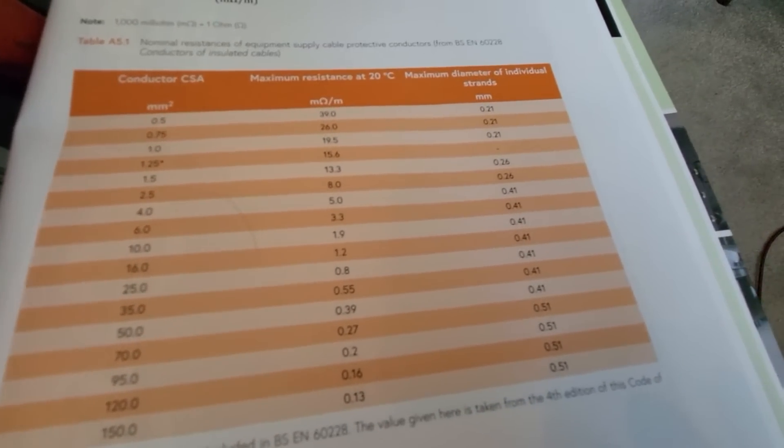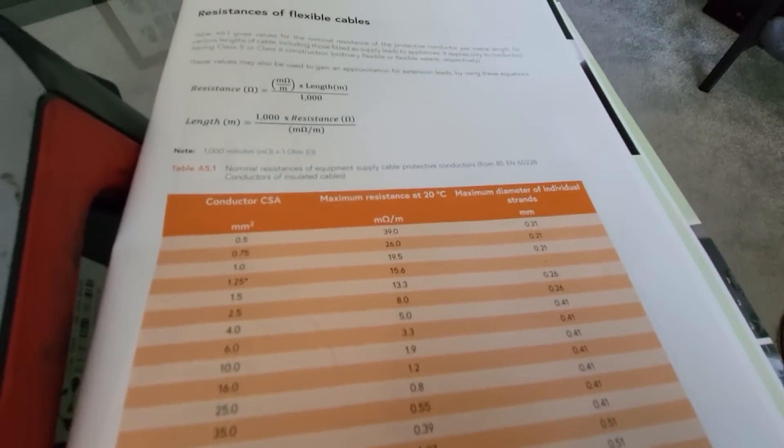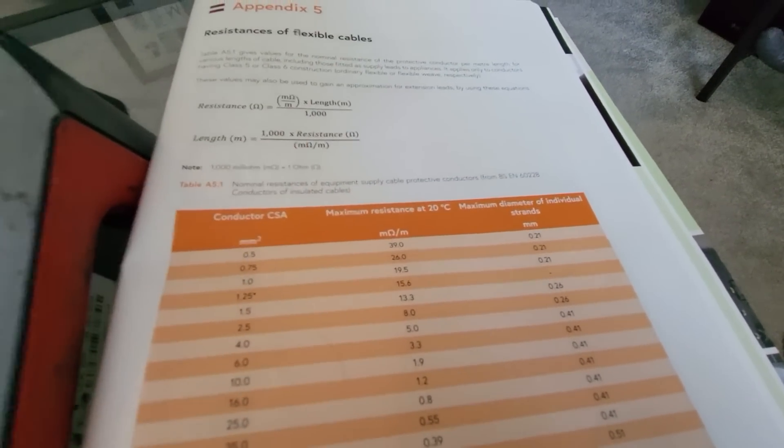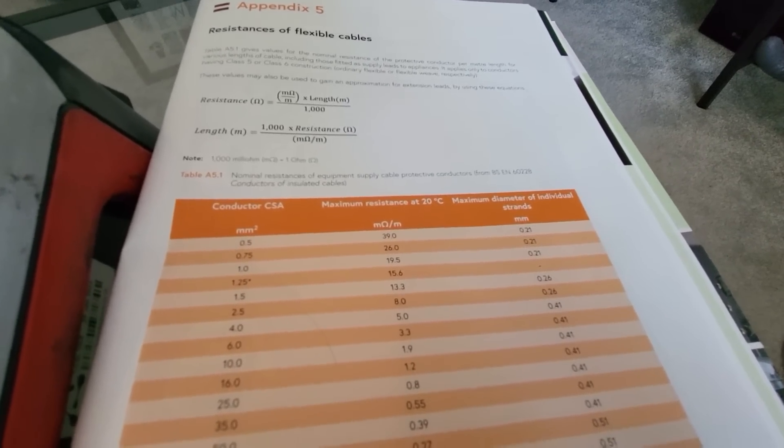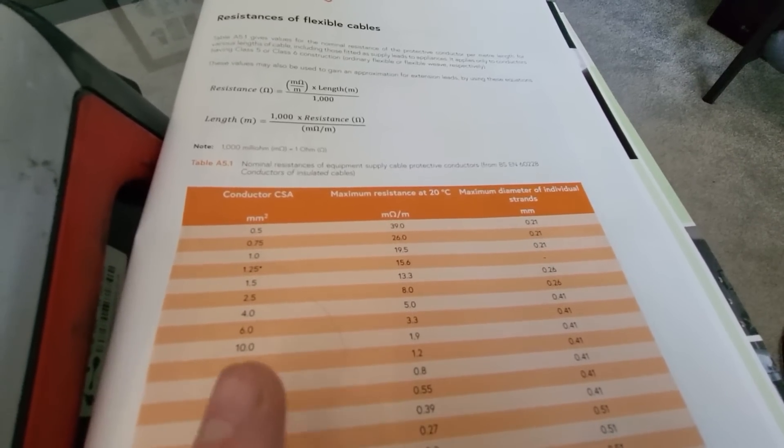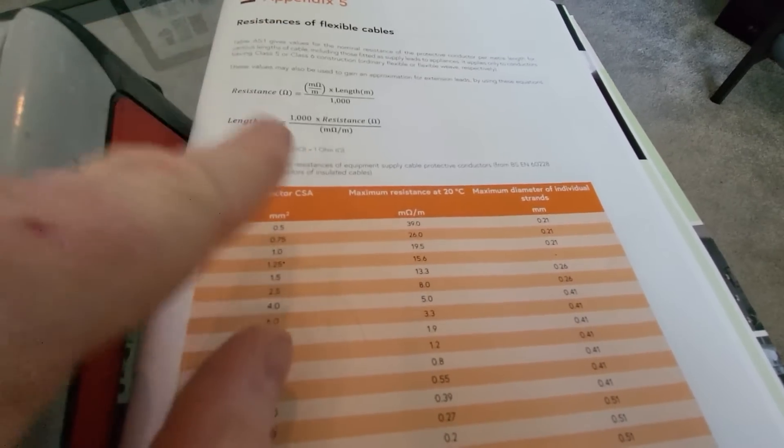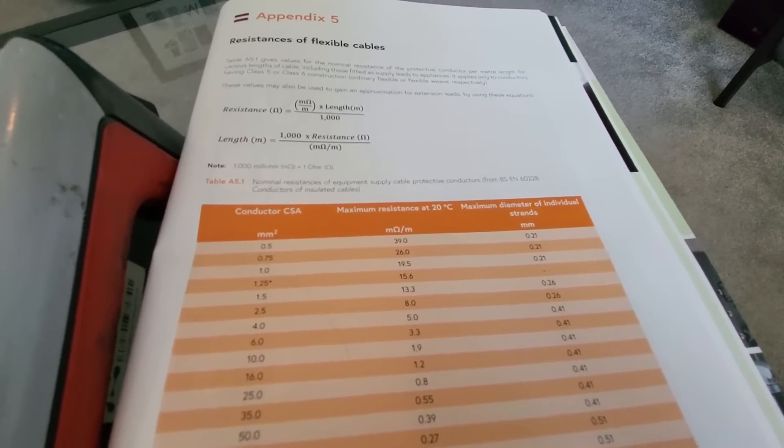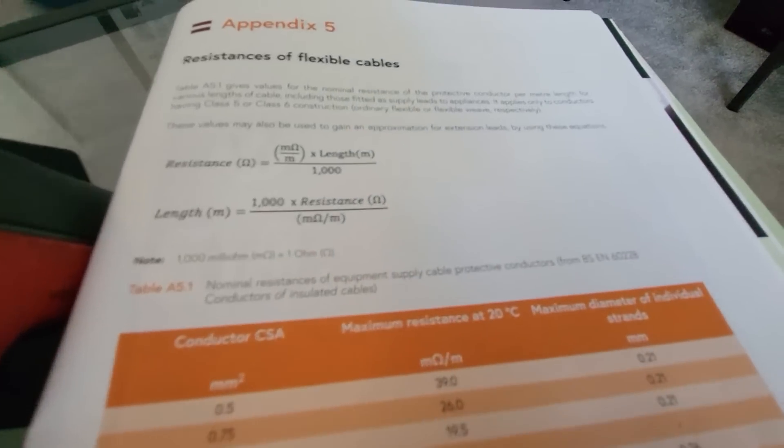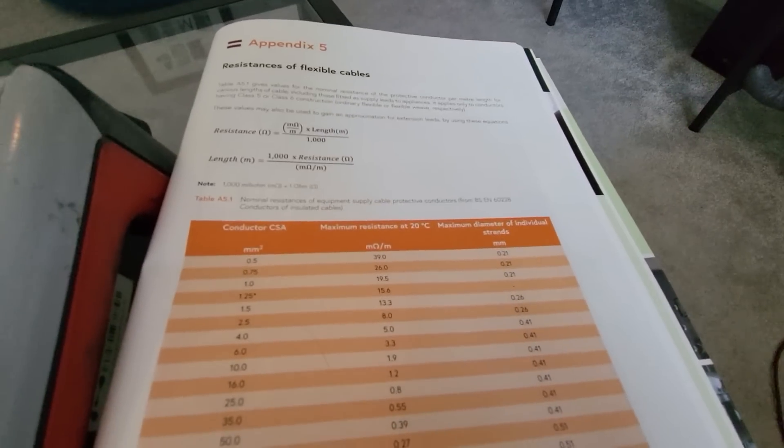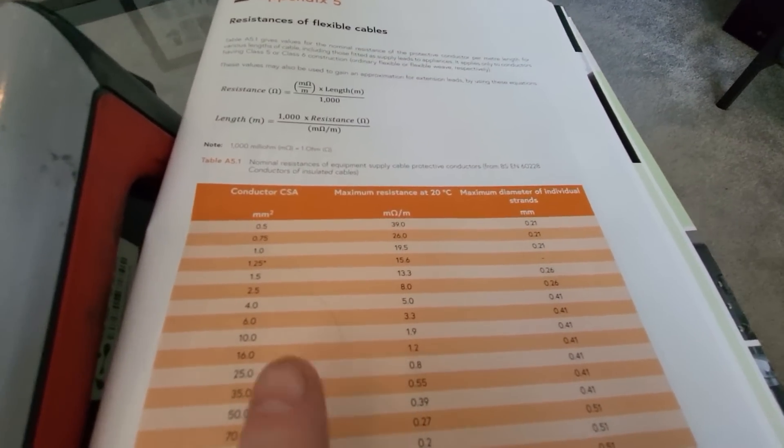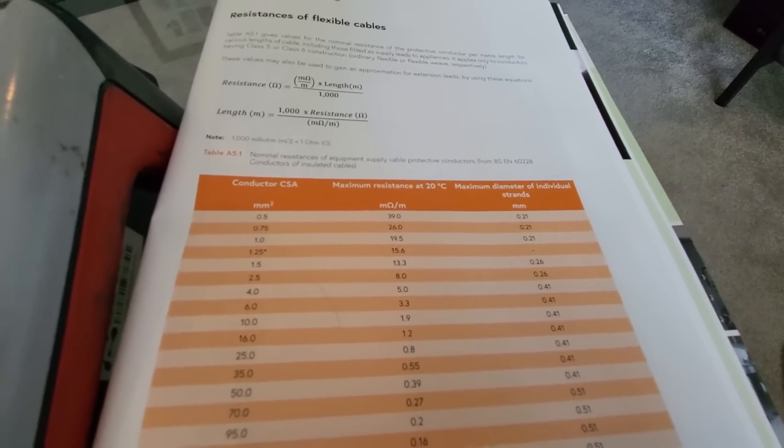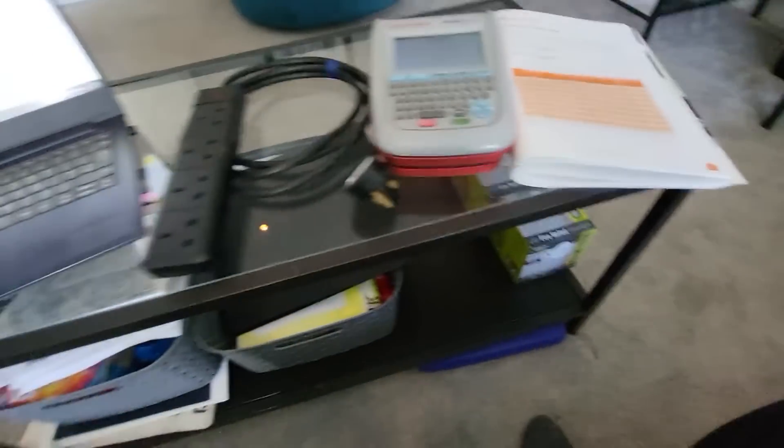And then it will give you the resistance there. You'll see that per metre, but you'll need to use the little table and diagram there to work out if you've got a particular length of extension lead, say a 1.5 extension lead at 10 metres. Use that calculation there. That will give you your resistance reading for a particular cross-section of cable at whatever length cable you have. And then you can cross-reference that against your PAT testing machine.